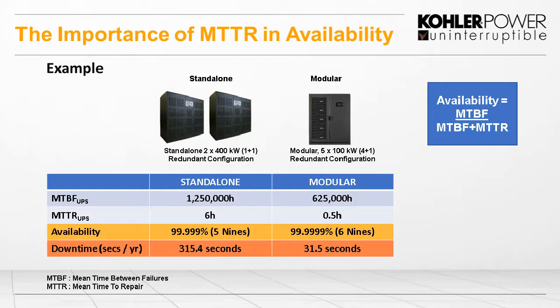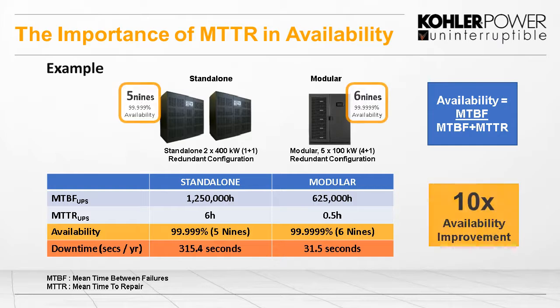So when we put that in the calculation of availability, the MTBF over the MTBF plus the MTTR, we get availability of 99.999% for standalone and 99.9999% for the modular, 6 nines. And when we calculate that in downtime, we have a 10 times availability improvement because of that MTTR. And you can see the downtime goes from 315 seconds down to 31.5 seconds for that type of UPS.